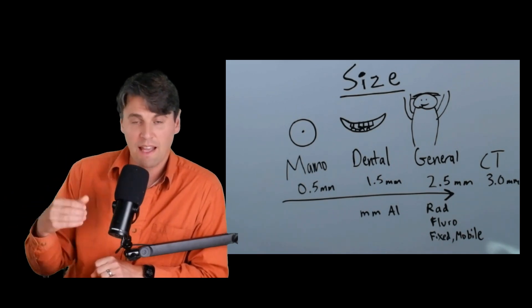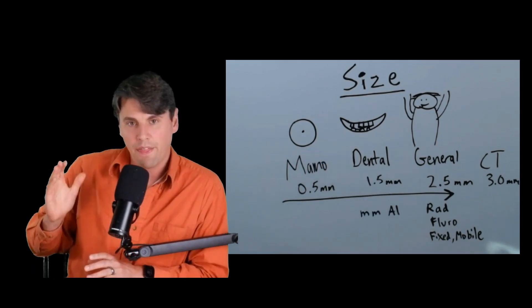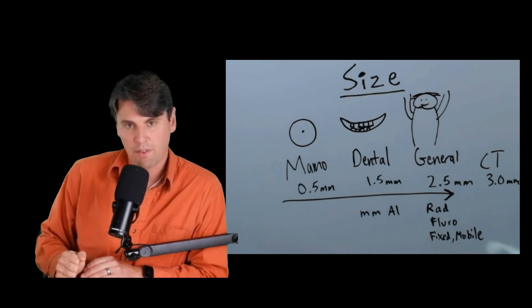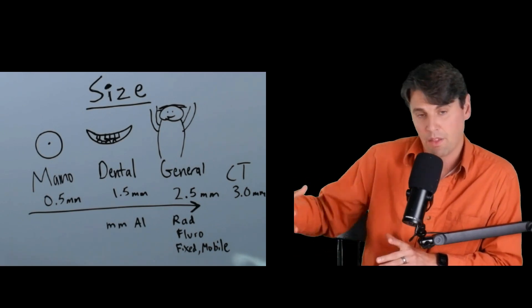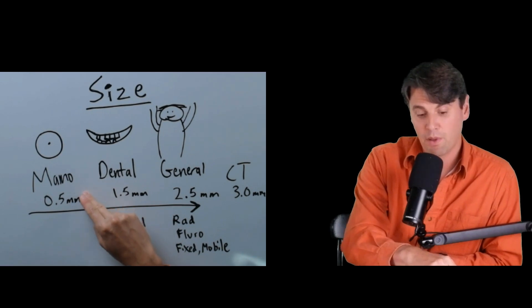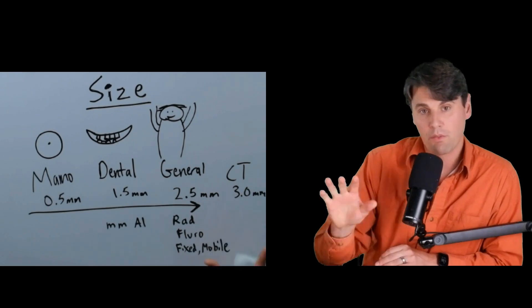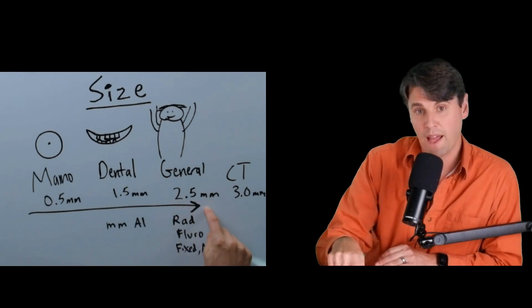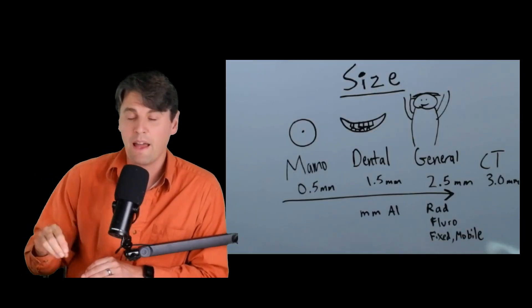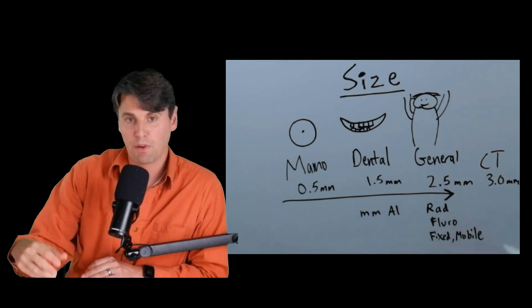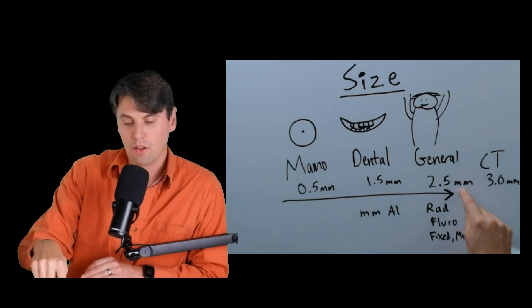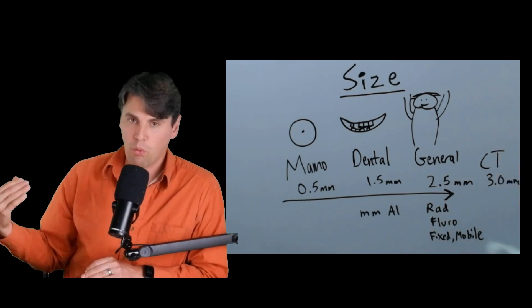For mammography — imaging a small object like the human breast — the limit is 0.5 millimeters of aluminum. For dental, it's 1.5 millimeters of aluminum. The key number to remember is the general purpose radiography requirement: 2.5 millimeters of aluminum, which applies to both fixed radiography systems and fluoroscopy systems where you're imaging through a regular-sized person. In CT, where we're always trying to penetrate through and take multiple views, the requirement is 3 millimeter aluminum equivalent for pre-patient filtration.